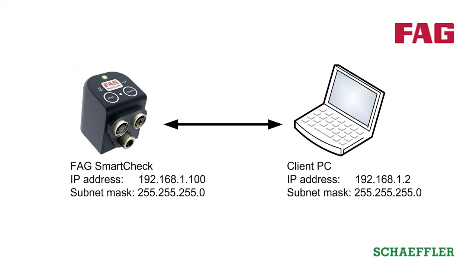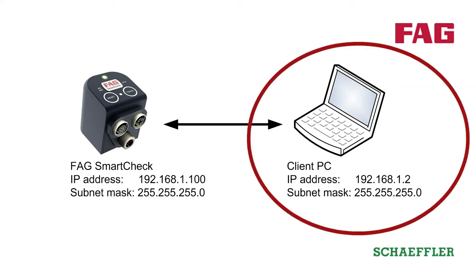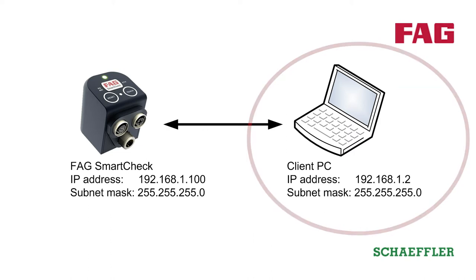So that the PC can communicate with the FAG SmartCheck, the IP addresses of the PC and FAG SmartCheck must be in the same range. Please observe the corresponding guidelines in the manual. In this case, we will enter the address 192.168.1.2 for the PC.